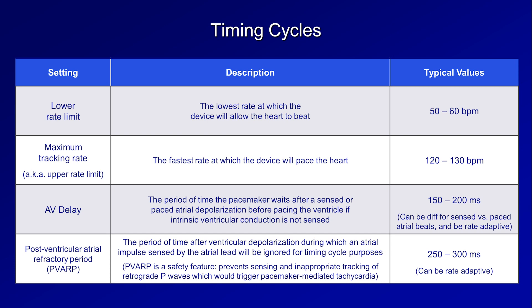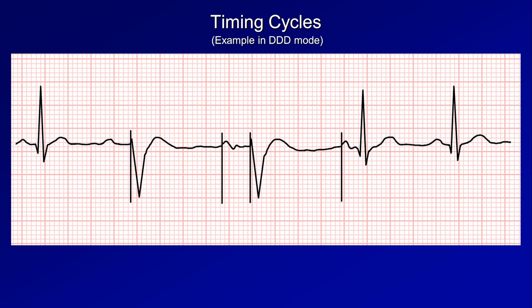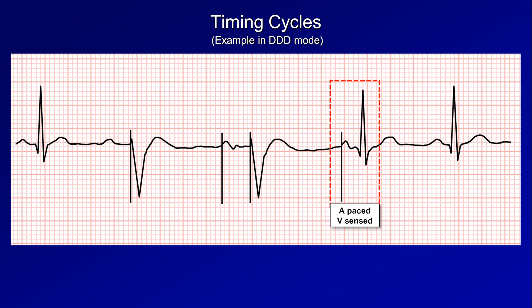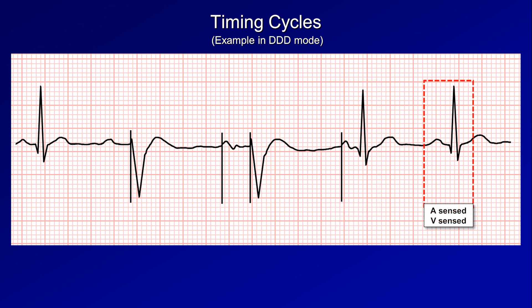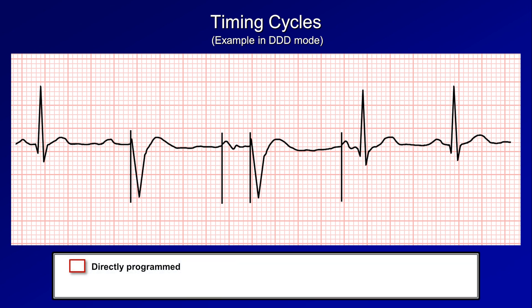Taking a closer look at how these settings determine the timing of cardiac events. Here is an example ECG for a patient in DDD mode, with a mix of A-sensed V-paced, A-paced V-paced, A-paced V-sensed, and A-sensed V-sensed beats. The four timing settings already discussed are directly programmed into the pacemaker, while a few other values are subsequently determined indirectly.